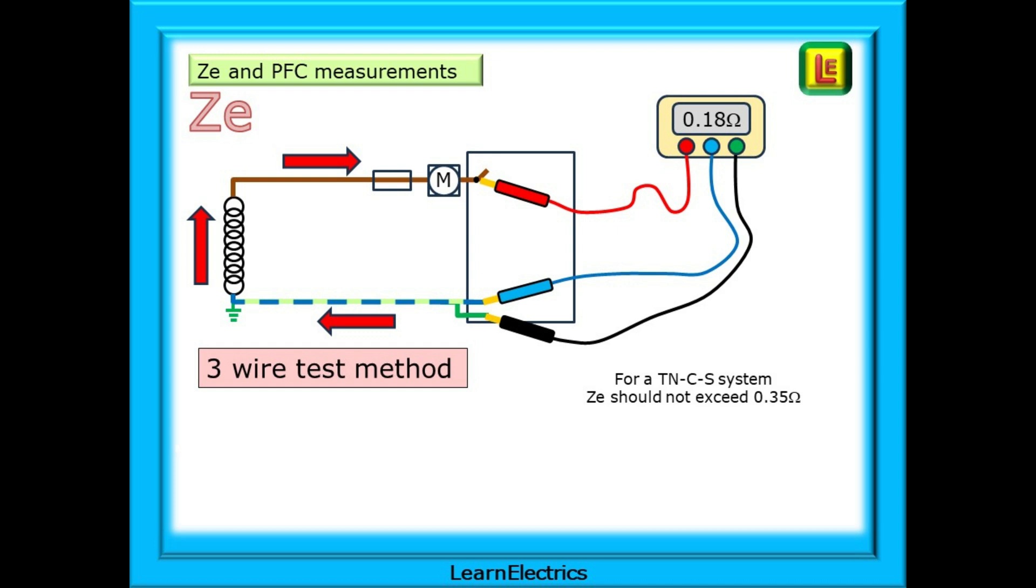With the main switch open and the main earth removed to avoid parallel paths, we can test between the removed earth, the neutral, and the incoming live side of the main switch. This is a three wire test and many meters do it this way - they use all three test leads. The actual test is between the line and earth but the test meter needs the neutral connection before it will start the test. A number will be returned after a few seconds and this should be recorded. The assessor may ask you what this means. In this example here the impedance of the earth fault loop path out of the building and back again is 0.18 ohms and should be recorded as ZE.